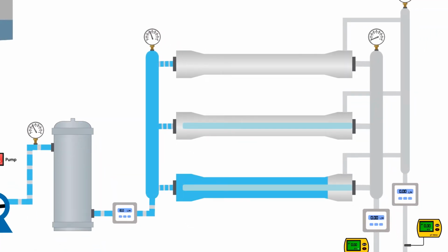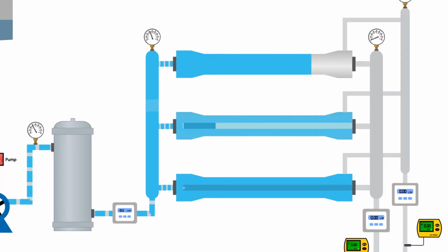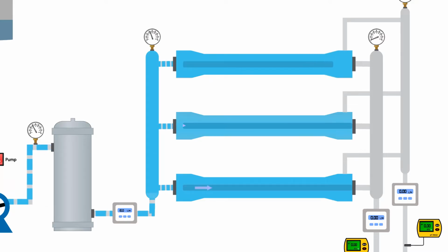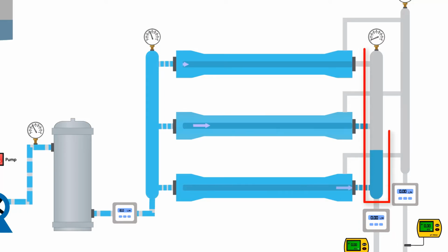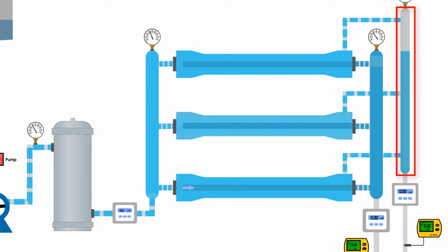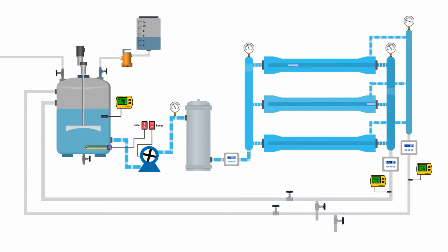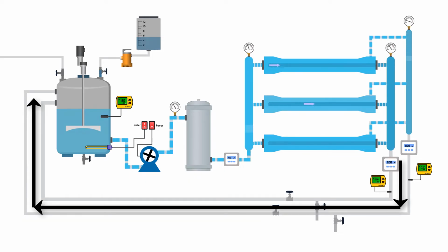As the solution passes through the membranes, it interacts with the stuck microbiological and suspended particles present in the membranes and tries to dissolve them. Each membrane has 2 outlets, permeate and reject. Permeate goes to the permeate header, while reject goes to the reject header. Both headers are connected to the mixer tank, meaning they continuously feed the solution back to the mixer tank.